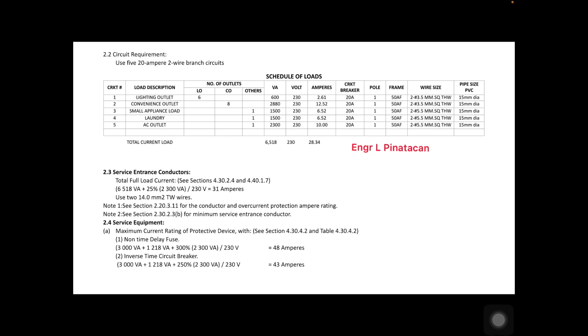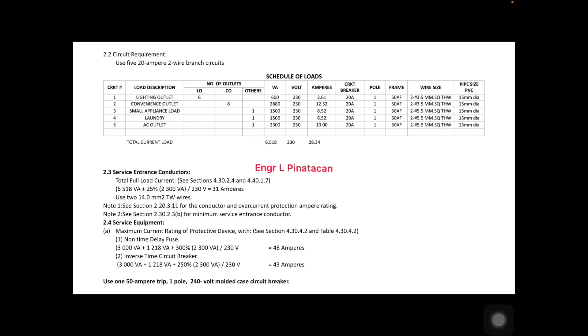For the non-timed fuse, we sum all the apparent power plus 300% of the highest apparent power on the circuit, divided by 230 volts, giving 48 amperes. For the inverse time circuit breaker, we sum all apparent power plus 250% of the highest apparent power, divided by 230 volts, giving 43 amperes. The Philippine Electrical Code recommends a 50-ampere, one-pole, 240-volt molded case circuit breaker for this system.